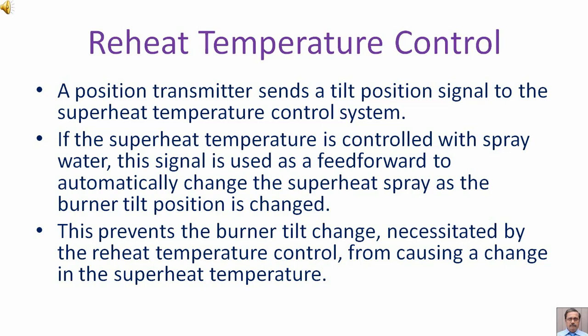A position transmitter sends a tilt position signal to the superheat temperature control system. If the superheat temperature is controlled with spray water, this signal is used as a feed forward to automatically change the superheat spray as the burner tilt position is changed. This prevents the burner tilt change necessitated by reheat temperature control from causing a change in the superheat temperature.